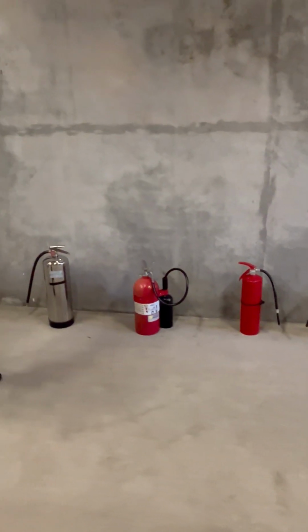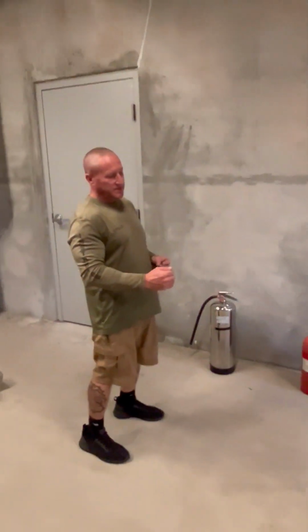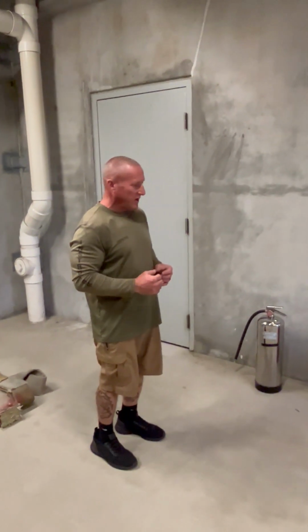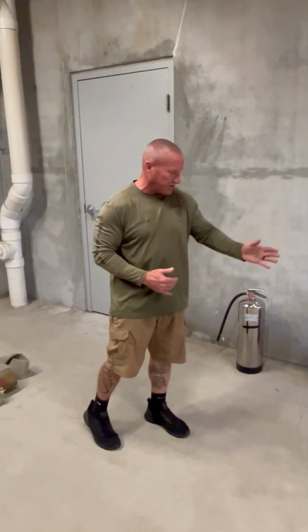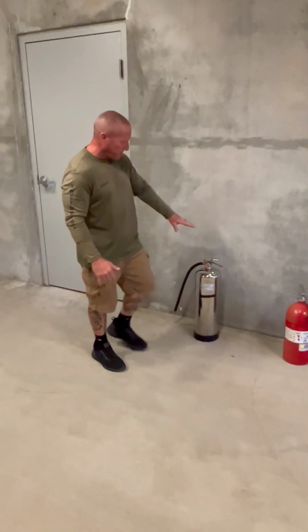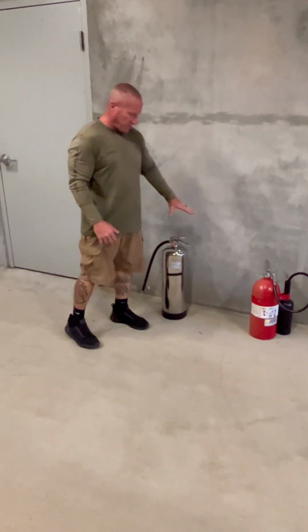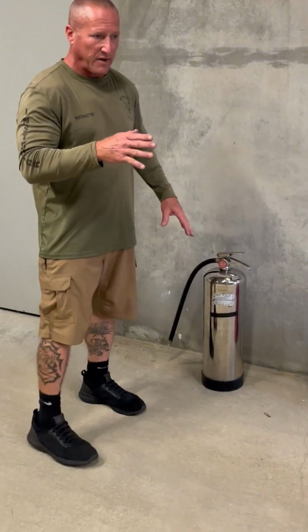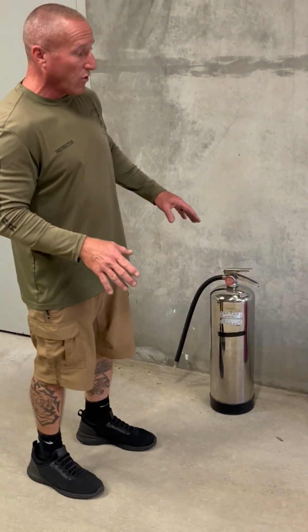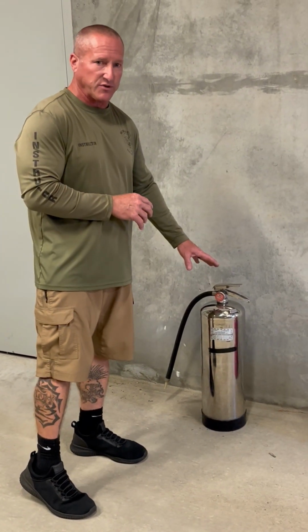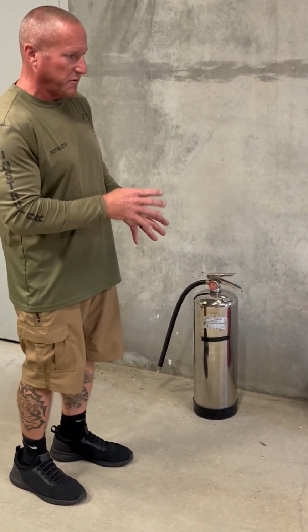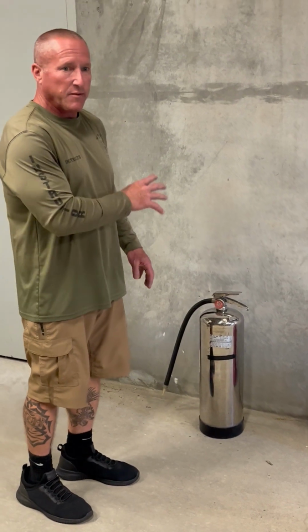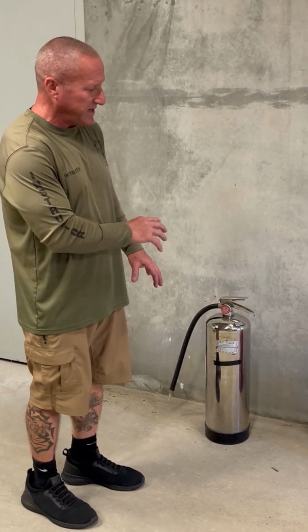A Class D fire will be my metals, and a K fire would basically be a kitchen fire that we would have to deal with. So knowing that type of fire then allows me to pick the proper extinguishing agent. I have a 2.5 gallon water can here. This could be a regular water can for my ordinary combustible Class A's, or this can have a foam additive to it, like an AFFF foam, that would allow me to work a little bit more with some of my B's, but still really with my A's, so for a Class A fire.